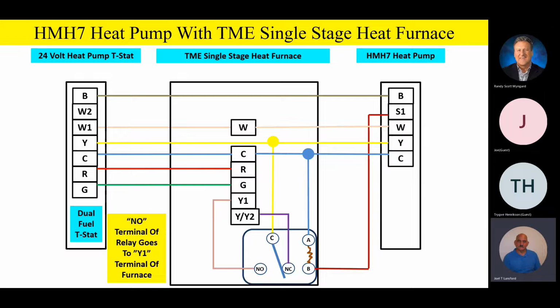That is correct. So that's an excellent observation and question, Randy, because it turns out that our TME single stage furnace has got two-stage cooling capability. Now that's something we really don't talk or advertise much, but even though it's a single-stage heating furnace, our simple TME still has two-stage cooling capability. Isn't that neat? And so that is correct. So even though it's a single-stage heating furnace, it does have two-stage cooling capability. Good observation.